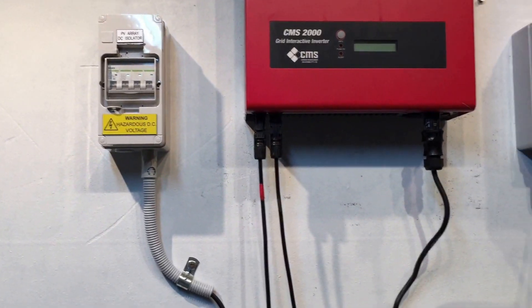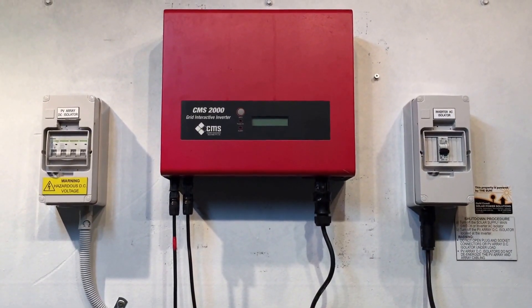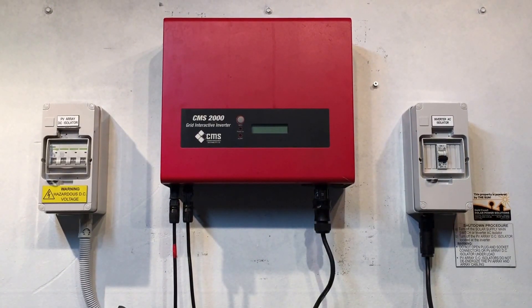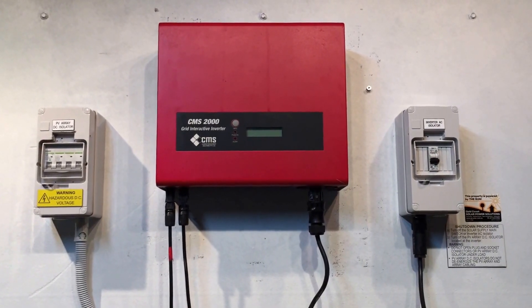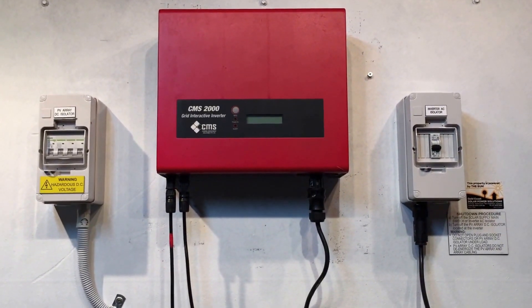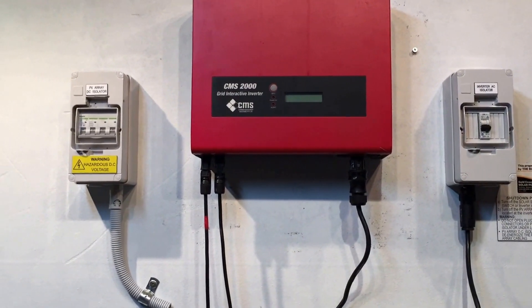We'll leave it a few moments and see if anything changes. What we're seeing on the screen here on the inverter is totally normal for night time. If the solar inverter is not detecting any power from the solar panels it's going to be in this mode. So this could be a problem with the solar panels, the wiring to the solar panels, or even the circuit breaker beside the inverter. We're just going to try and reboot this now.